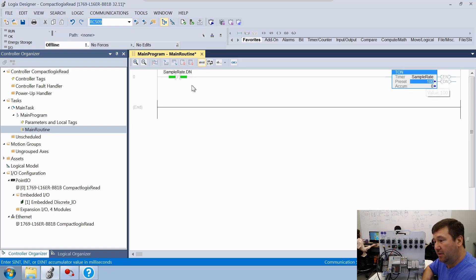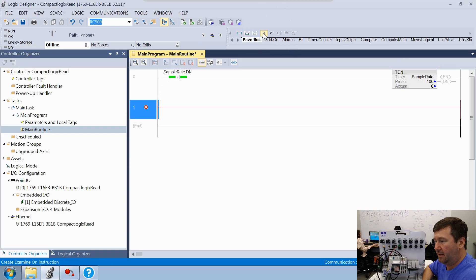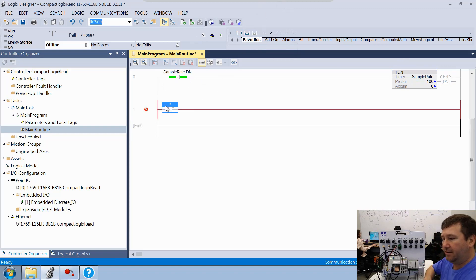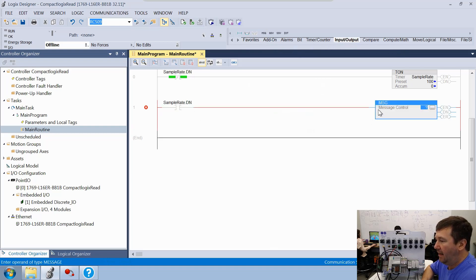What this is going to do is every 100 milliseconds, this timer is going to be done for one scan. And we're going to use that to trigger our message instruction. So we're going to add another rung and bring down an examine on instruction. We're going to look at the sample rate dot DN bit. And then we're going to use a message instruction.